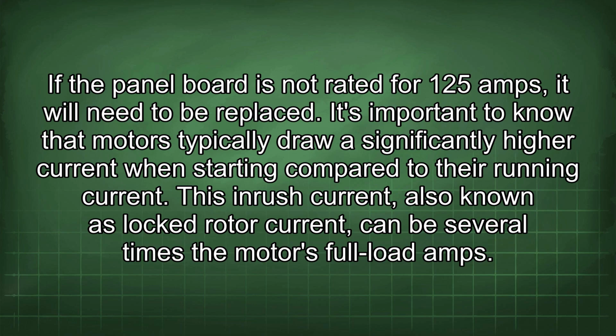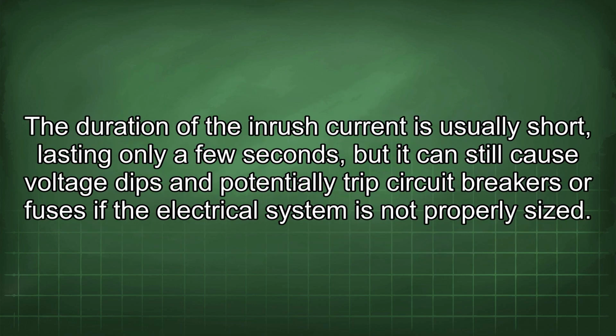It's important to note that motors typically draw significantly higher current when starting compared to their running current. This inrush current, also known as locked rotor current, can be several times the motor's full load amps. The duration of the inrush current is usually short, lasting only a few seconds, but it can still cause voltage dips and potentially trip circuit breakers or fuses if the electrical system is not properly sized.